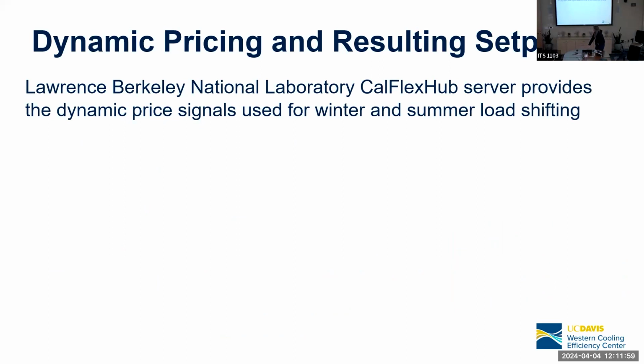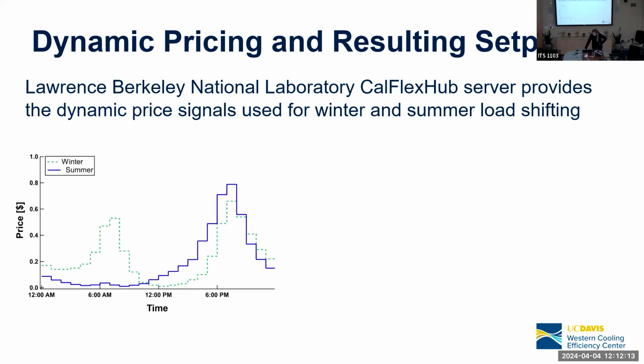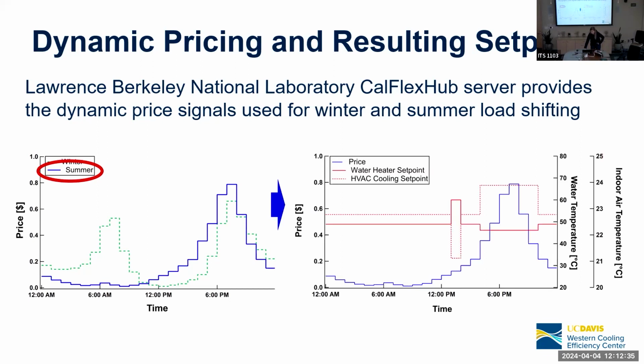Right, so we'll go step by step. All right, so the price signal that we're getting is coming from Lawrence Berkeley National Laboratory. It's from the CalFlexHub server, and we are looking at summer, but here's the price signal for both winter and summer. So summer has a single peak in the evening hours, and then winter has 2 peaks, one in the morning and one in the evening, because a lot of times you have heating load early in the morning when it's cooler in winter. We're looking at summer, so taking that summer signal and translating it into our set points, we can see here that we've got a load up event at around 1 o'clock for both the water heater and the HVAC.